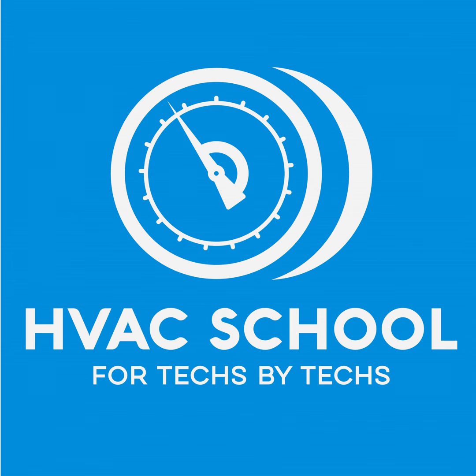The other cool thing is we've got our standard VRV4, which is our standard heating unit, and the Aurora. They both utilize the very bottom circuit of that outdoor unit as hot gas all the time. And it's doing two things. So the main thing is I want to make sure that as I go into defrost and things like that, I don't want ice or that moisture to freeze back into ice. So I keep that bottom row hot all the time to make sure there's no ice being built up. The other thing it's doing, once it condenses into liquid, it's cooling the inverter board. That refrigerant's passing on the backside of that inverter board, keeping it at a more consistent temperature, regardless of what our outdoor ambient and condenser fan motors are doing.